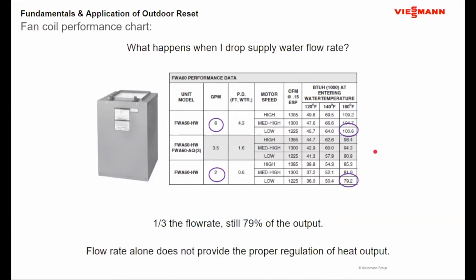So again, when somebody says, well, what about varying the speed through the heat emitters? The problem is you generally don't get a good proportional change. I can drop the flow rate quite dramatically, but the output stays fairly consistent, not giving me the level of response that I'm really looking for from a control strategy. Okay. So we have to look elsewhere.